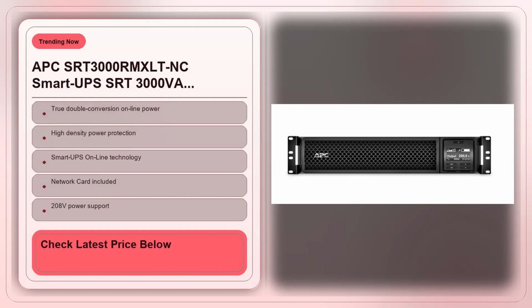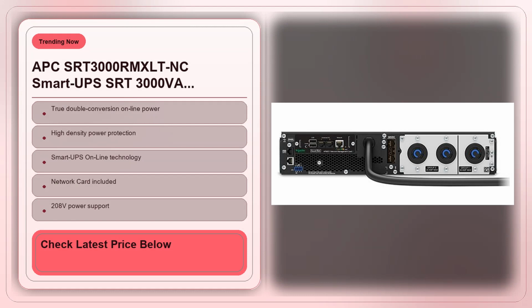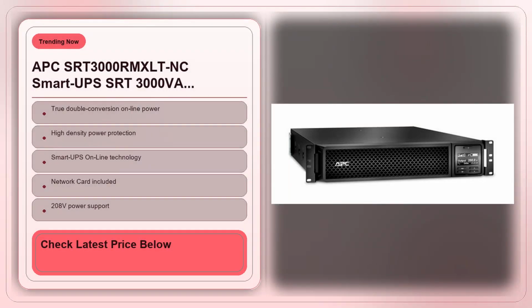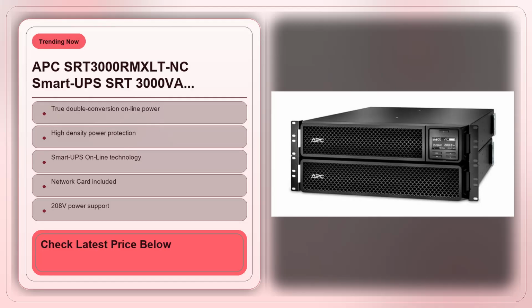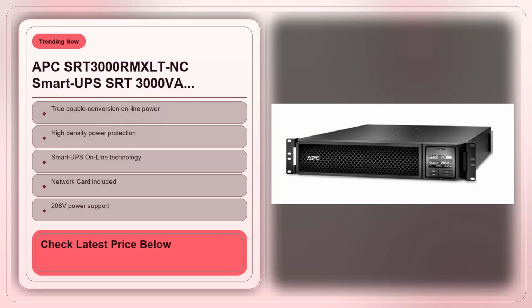But no product is perfect, and this one has a few hidden trade-offs that matter once you have it in the rack. The SRT's high capacity comes with a relatively high idle power draw. Even when you're only using 10% of its rated load, the UPS itself consumes enough power that the overall efficiency drops compared to a smaller unit running at a higher load factor. That's something you'll notice on your monthly electricity bill if you keep it running constantly.